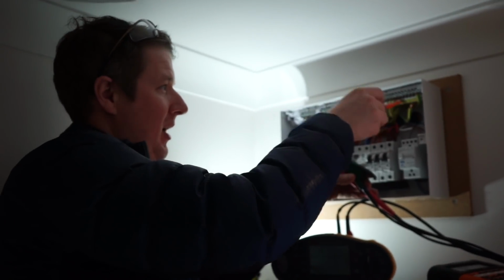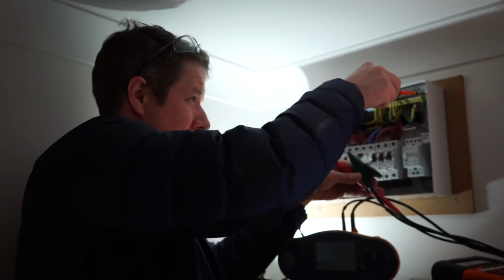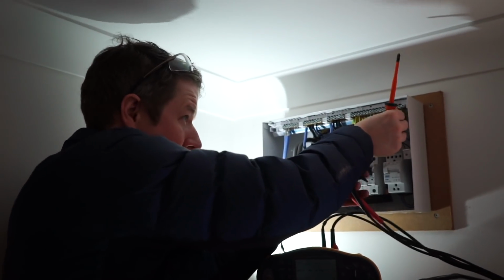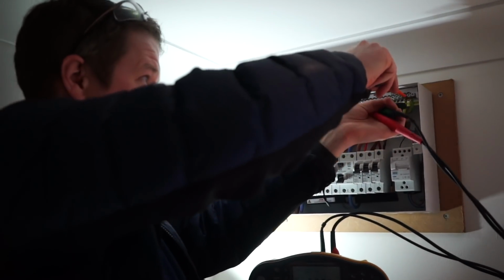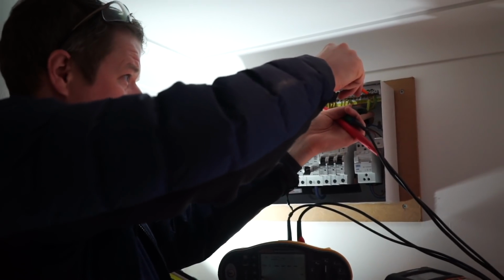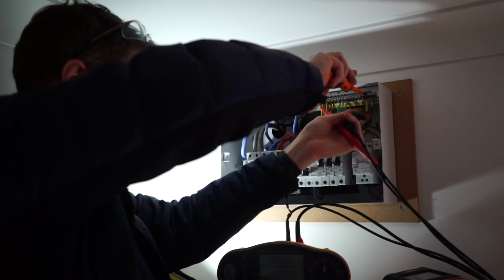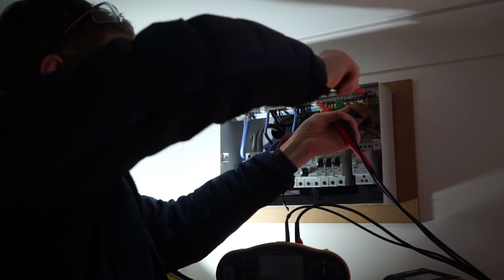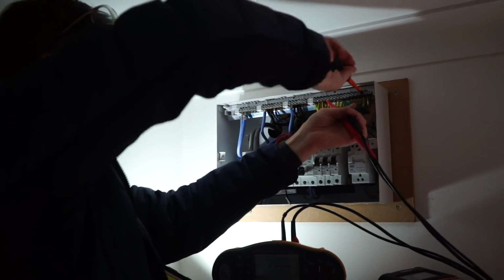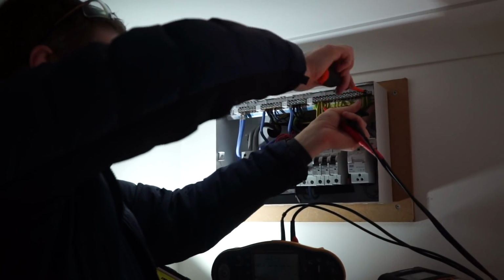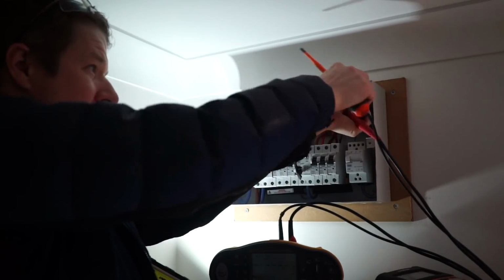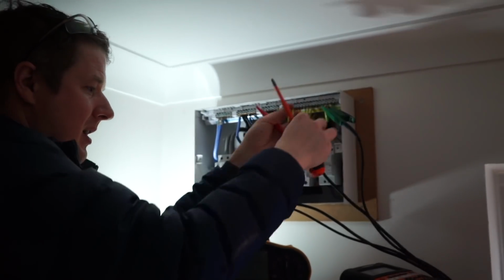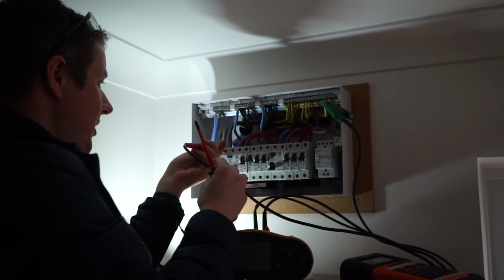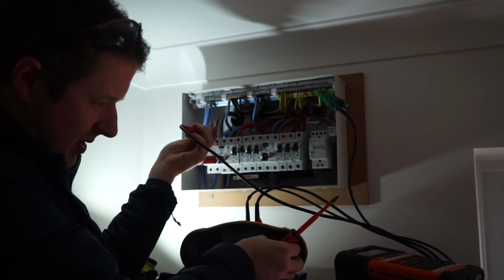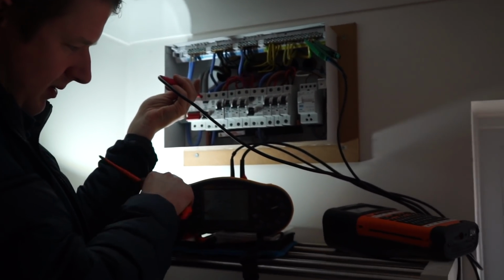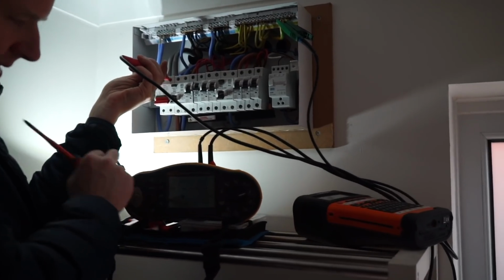So this is the main incoming earth. So what we do is, actually, let me do it this way. We have to disconnect all bonding conductors when we're doing an external earth fault loop impedance. So usually I would just disconnect the bonding conductors, but in this case, because there's 2 of them, I would just disconnect the main earth instead and do it like that. So we just get onto there, and then we get onto the main live tail coming in, and we do it on the high current earth loop impedance test.